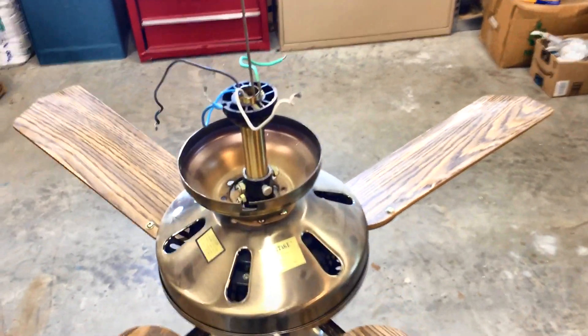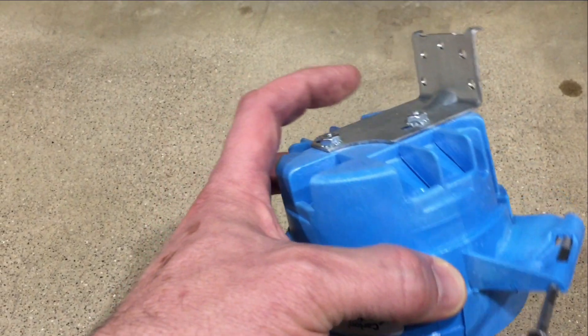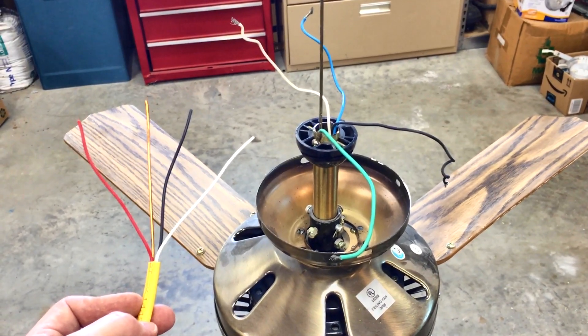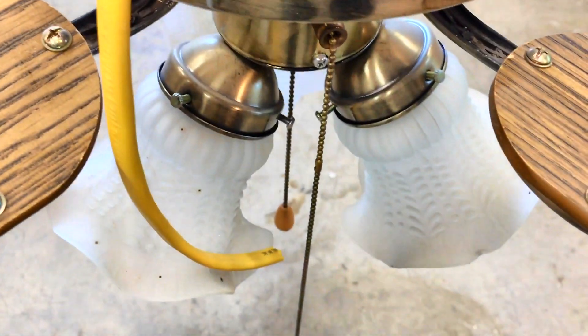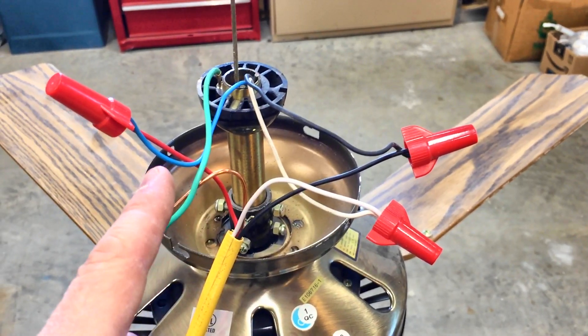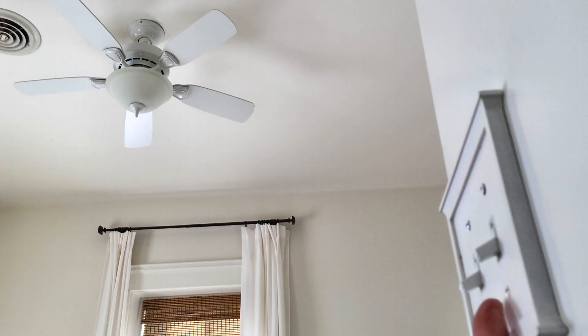Ceiling fans are actually very similar to lights. Since ceiling fans are so heavy, you have to use this special box with the bracket on the back. There's also a special ceiling fan wire that has the white, black, and copper that we're used to, but adds this new red wire. You wire black to black, and that controls your light. Red to blue, and that controls the fan motor. White wires are neutral, and green to ground. On the other end of this wire, the black and red go to two switches so you can control the fan and light separately.